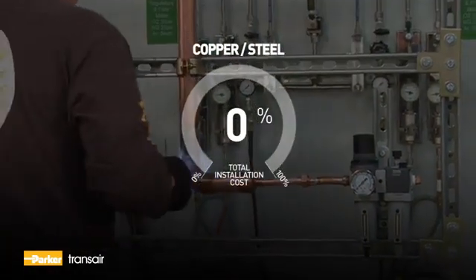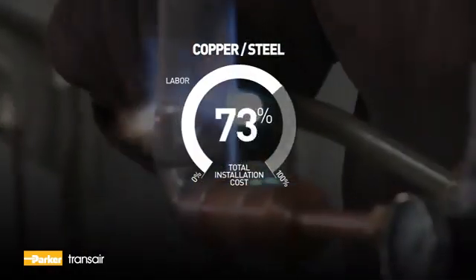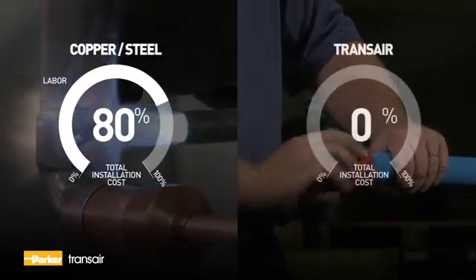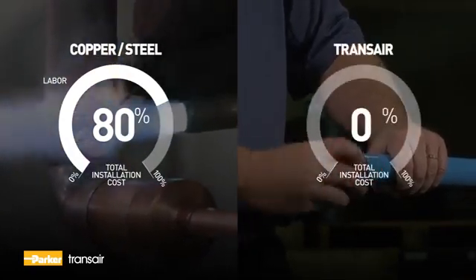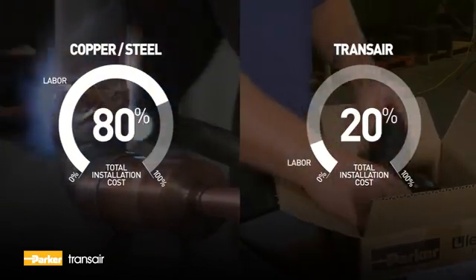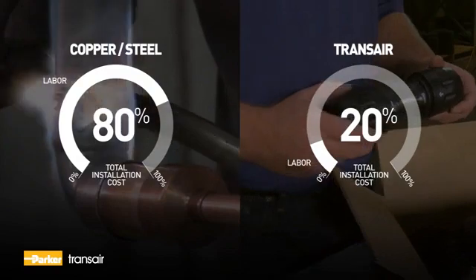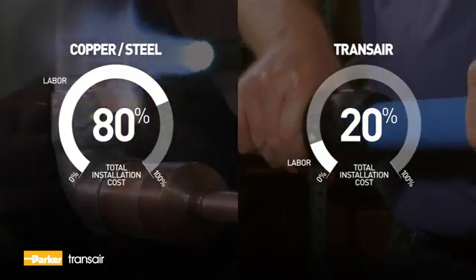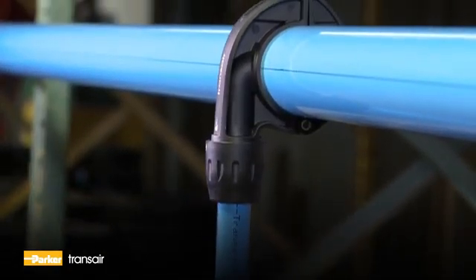With steel or copper, labor accounts for 50-80% of the installation cost, as compared to Transair, which accounts for only 20% of the installation costs. This is possible by making connectors that are ready for immediate use. For pipes one and a half inches and less in diameter, simply push the connector onto the end of the pipe. There's no need to tighten the nut. It's that easy.